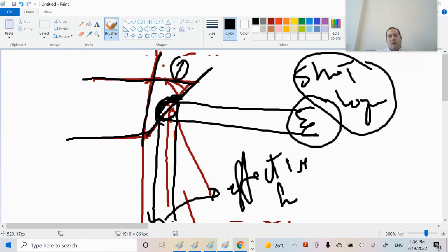Whenever you have a narrow, focused, and very precise electron beam, the heat loss on the anode is concentrated in a single specific spot, rather than being distributed. Ideally, it should be concentrated in a singular area, meaning that the smaller you make the focused electron beam on a very small, confined area within the anode, the more problematic your thermal distribution becomes.